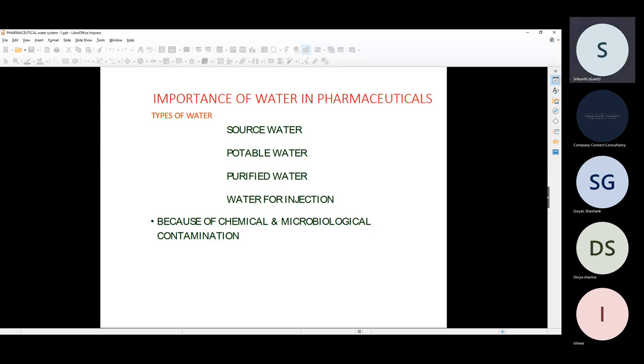We should also calculate the organic carbon in the water. Why? Carbon is a good source, a good food for the microorganisms. If the organic carbon is higher, there is a huge chance of an increase in the microbial load. It's food for the microbial organisms, so we have to control the TOC also. The guidelines say it should be less than 500 parts per billion, ppb. We will have online parameters and offline parameters. Online sensors and offline QC will also test for that. So we have to ensure that these things are in control.